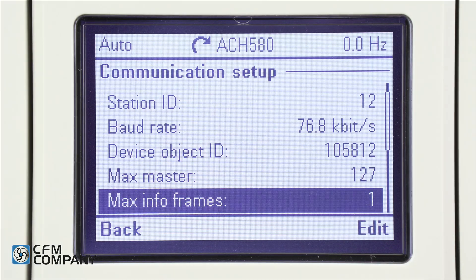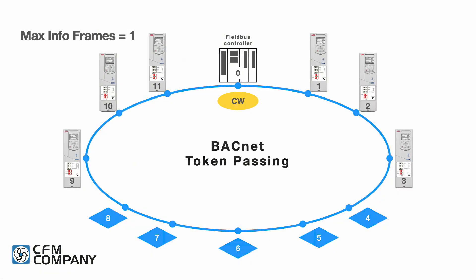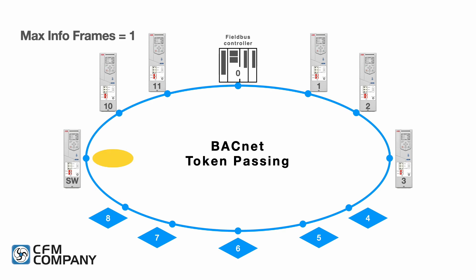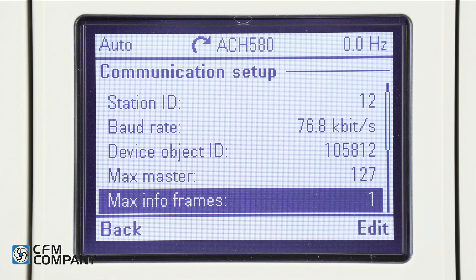Next is max info frames. Press the question mark button. This is the maximum number of information frames the device may transmit before it must pass the token. Press exit. This device is restricted to only transmitting one piece of information before it must pass the token to the next address on the network. If every device on the network is programmed to pass only one piece of information at a time, the token can be passed along rapidly — it is this efficiency that can make it possible to transmit large amounts of data fast on the network. Leave the max info frames at the default value of 1.